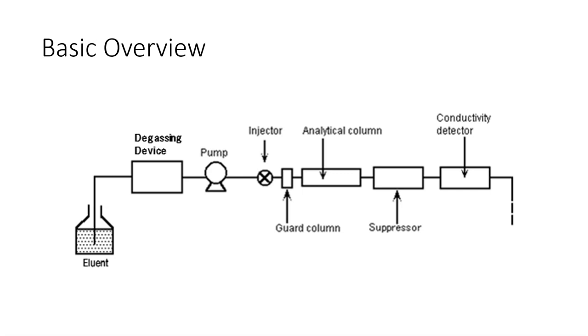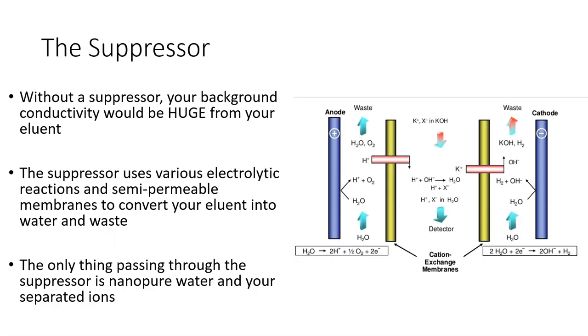They need to make their way to the conductivity detector to be measured, but there's one more very important component before we get there—this is the suppressor. Without a suppressor, your background conductivity would be huge from your eluent. We're using acid and base concentrations in our eluent, and that has a lot of conductivity, so we need to suppress that first.